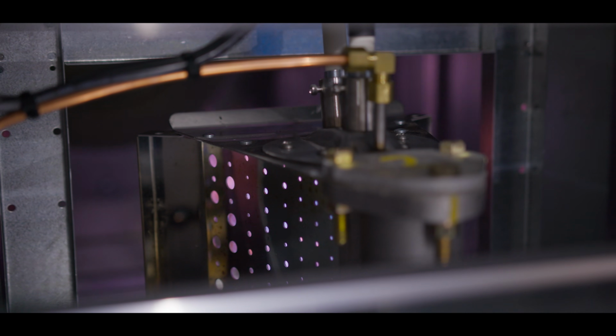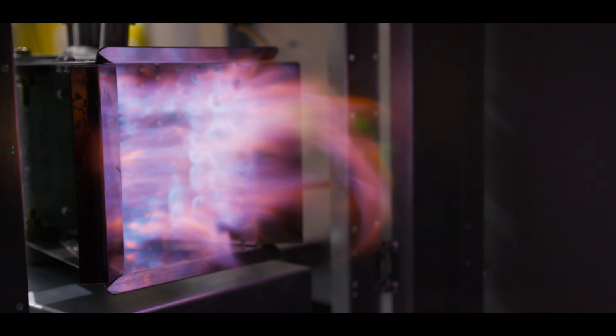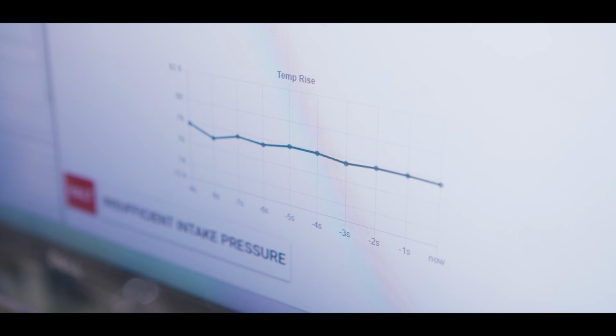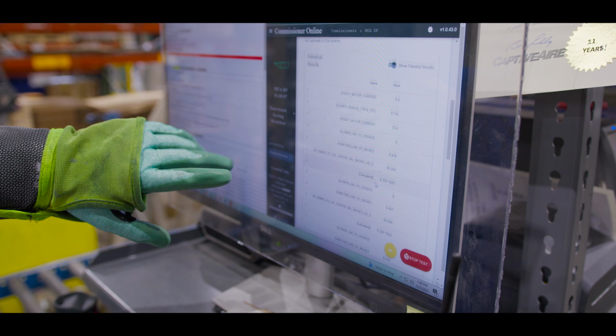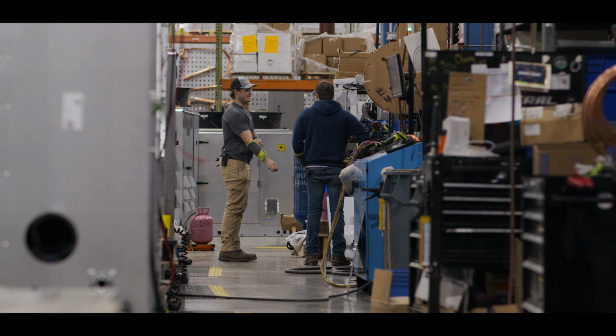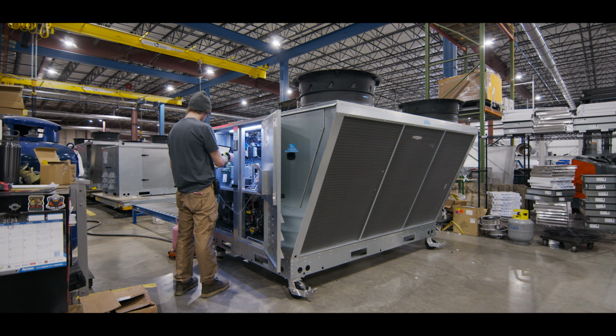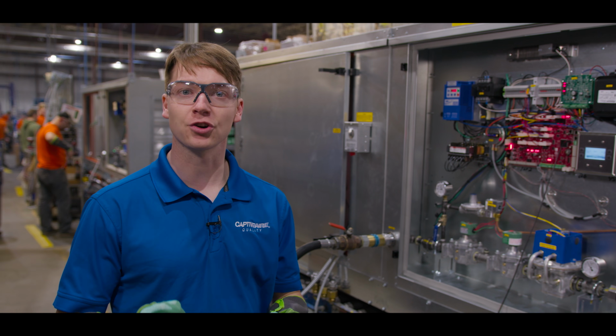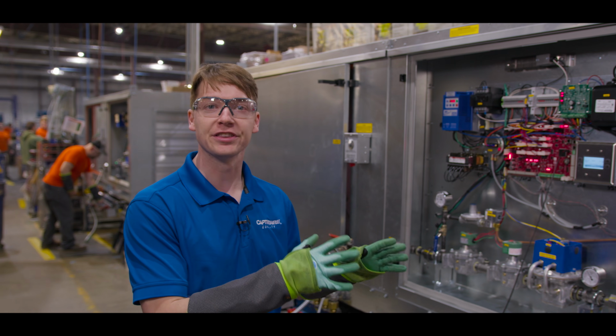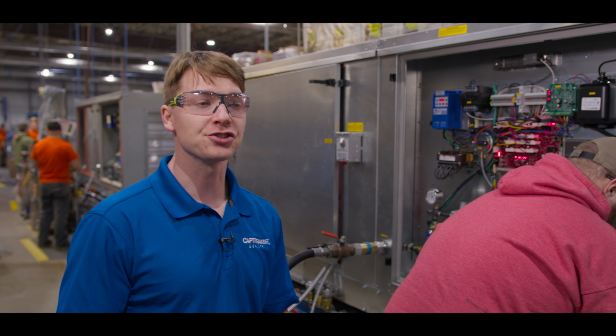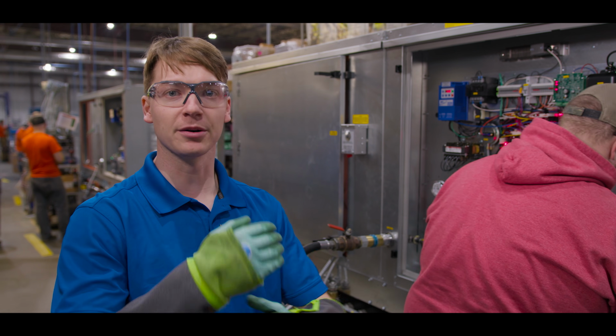So if we can build in a system that no matter what, when this is ran, when the blowers ran, when the heaters ran, we're digitally recording all of those temperatures, making sure they're within a certain degrees of each other, making sure that your discharge sensor is wired to your discharge and installed in your discharge location. If we can automate that and let the individuals focus on the tasks that matter, then let's do that. Let's automate that process. Something with automated testing is that sometimes people are hesitant to trust software. They'll say, how can I know that this is actually reading what it should? And we are actually doing both manual with software, so it's a double verification.